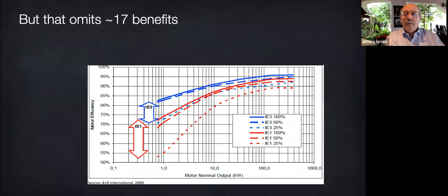But in fact, half of US industrial motors never exceed 60% of their rated load. A third of US industrial motors never exceed 50% of their rated load. So they're running much less efficiently than the full load nameplate rating says. Underloaded induction motors don't just run less efficiently, they also run faster. So they waste more energy in pumps and fans, cube law machines, because they drive more flow than needed, a lot more. And because of these two effects of pervasive oversizing, right-sized new motors will save more energy than expected from comparisons that consider only the nameplate efficiency gain, but not also right sizing.